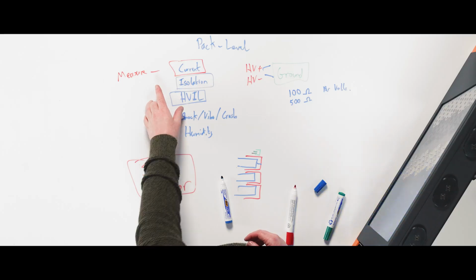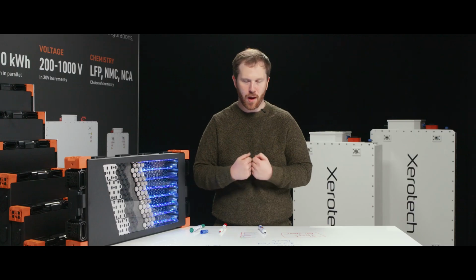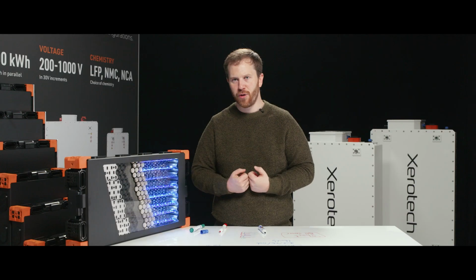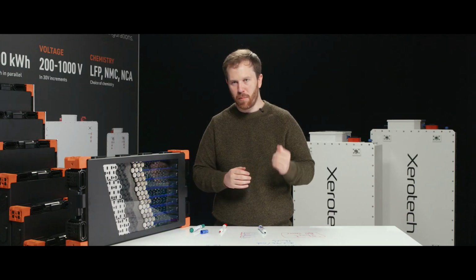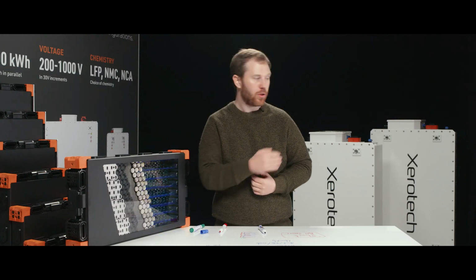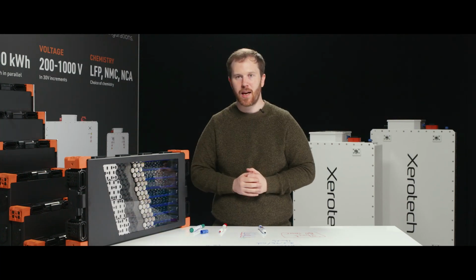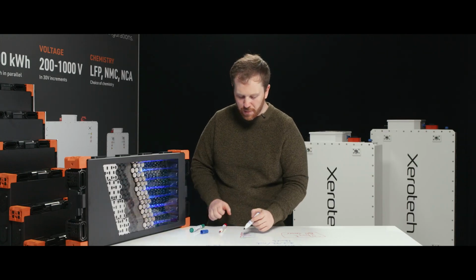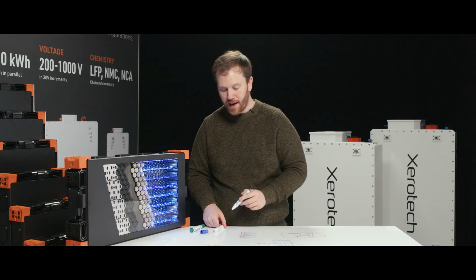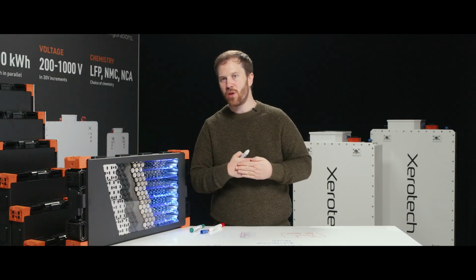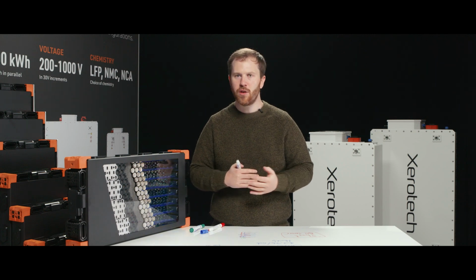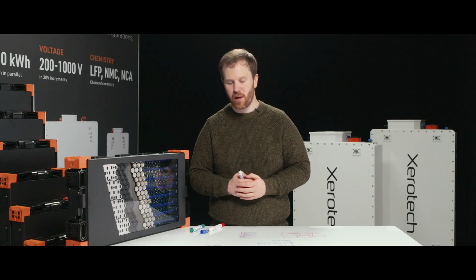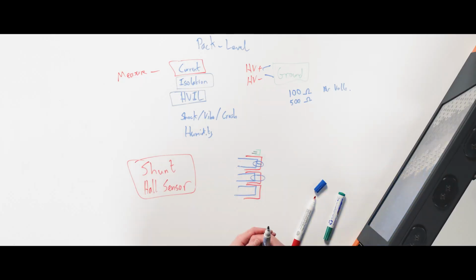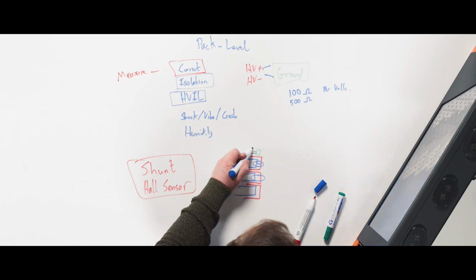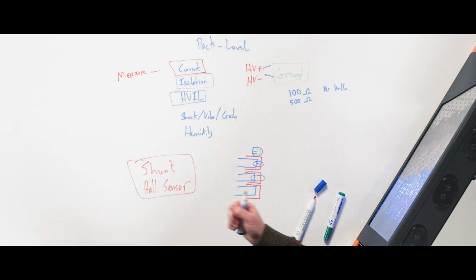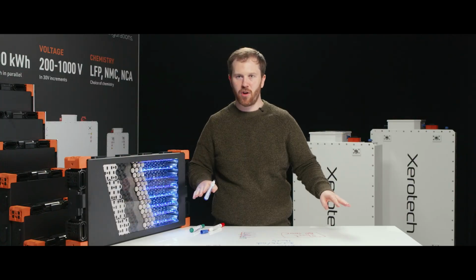So HVIL is very important. You do not ever, under any circumstances, break or open an orange connector under load. It will create a big spark and flash and will burn the connectors and can present a hazard to you. Battery systems will then emergency disconnect under load. But the problem is, this extremely destructive event that happens at the connectors actually even happens in the contactors to do it. So you should never break contactors under load. You can only do it 1 or 2 times before the contactors need to be replaced. So that is an emergency disconnect power down. The normal thing that happens in batteries is you get a HVIL loop fault, and the BMS will immediately signal all other parts of the system to stop drawing load immediately.